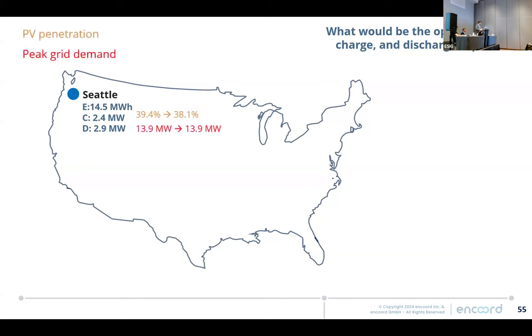And as we see, the impact of PV penetration is not large, neither is the peak grid demand, but we are able to build something more that can still increase the value of storage by customizing the ratio between energy charge and discharge. If we look at Phoenix though, this flexibility increases the optimal storage size 2x, more than 50 megawatt hours. And what we see here also, the discharge is higher than charge. We have 7.8 megawatts of discharge, 6.4 megawatts of charge.